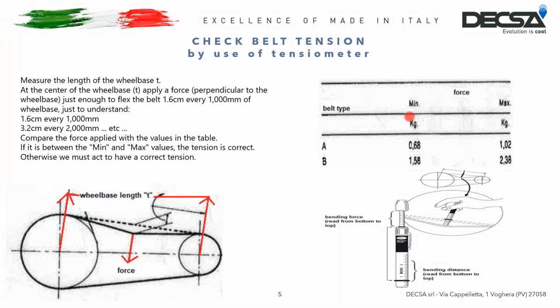Now we can start checking the belts by the procedure as following. As you can see, the wheelbase T is the distance between the center of the two pulleys. This distance must be reported perpendicularly on the belt and then calculate its middle point. At this point, we connect with a tensiometer, this device, to push the belt away from the near one by 1.6 centimeter if the wheelbase T is 1 meter long, 3.2, the double, centimeters if it's 2 meters long, etc.